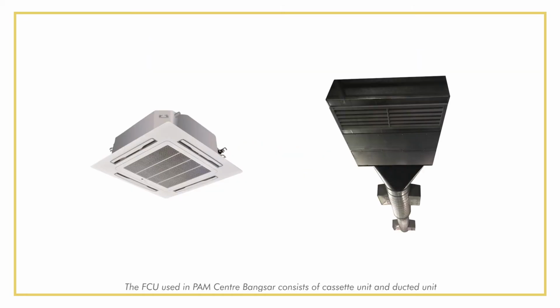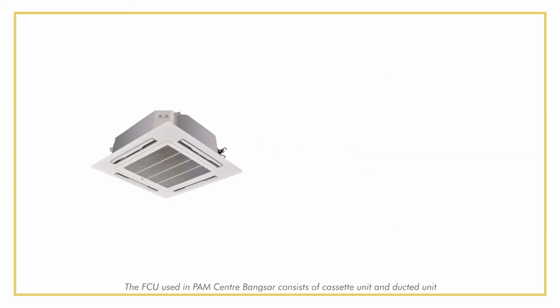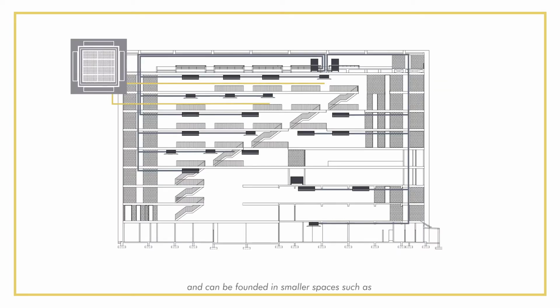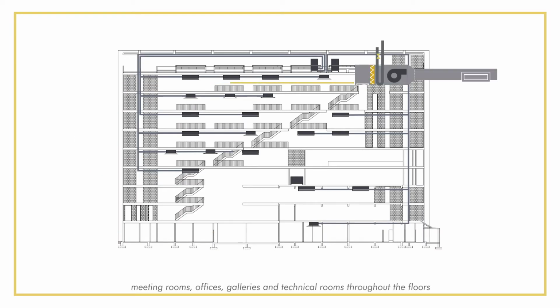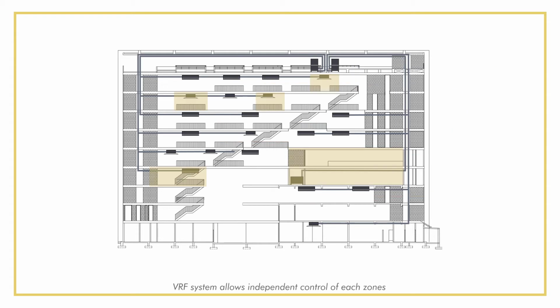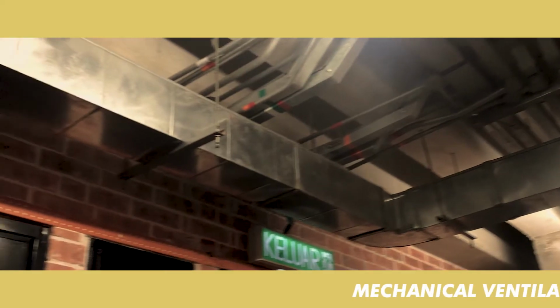The FCU used in PAM Center Bangsar consists of cassette units and ducted units and can be found in smaller spaces such as meeting rooms, offices, galleries, and technical rooms throughout the floors. The VRF system allows independent control of each zone to suit the different comfort levels of users as well as working times of the units, hence more efficient and energy saving.